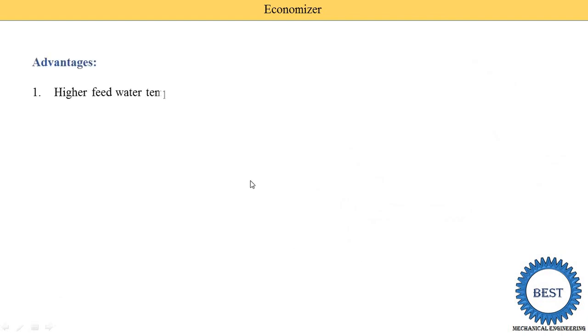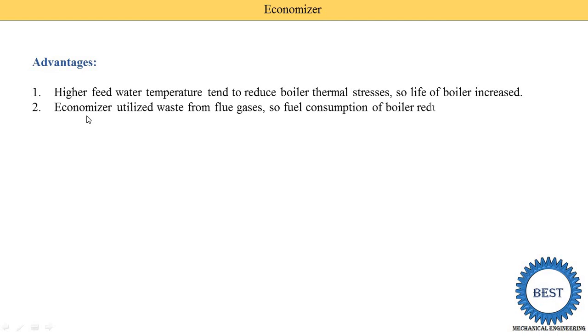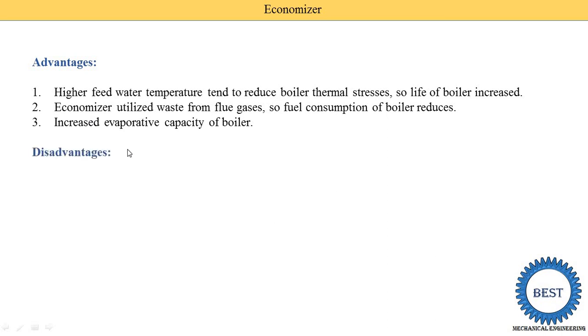The advantages of the economizer are: higher feed water temperatures tend to reduce the boiler thermal stress, so the life of the boiler is increased and boiler efficiency is improved. Economizers utilize waste heat from the flue gases, so fuel consumption of the boiler is reduced because water is supplied at higher temperatures, meaning the mass of fuel supplied is reduced. The economizer also increases the evaporative capacity of boilers, meaning it increases the steam generation rate.